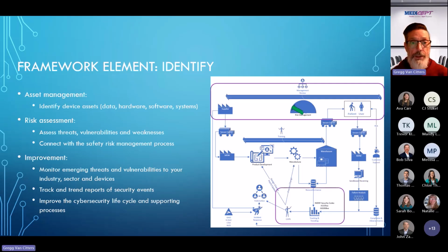You need to also understand the threat landscape. Who are those actors? How might they attempt to penetrate your device and wreak havoc? Threat modeling and analysis of known software anomalies and vulnerabilities helps you determine your attack surface and how attackers might get in. So you need to monitor those anomalies and vulnerabilities, not only during development, but after product release throughout the rest of the life cycle, including installation, maintenance, servicing, product decommissioning, and disposal. Everything needs to be secured.